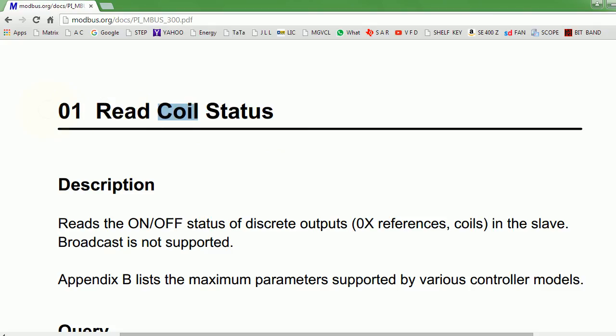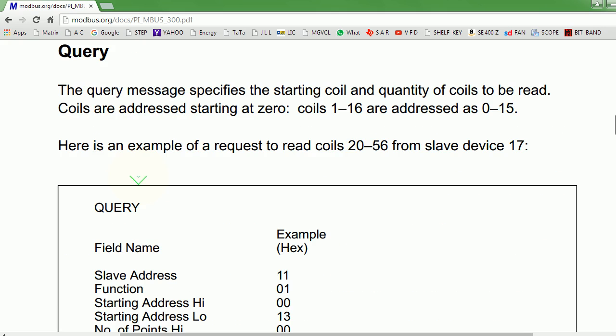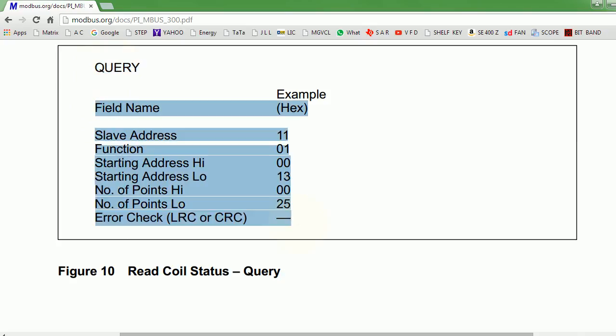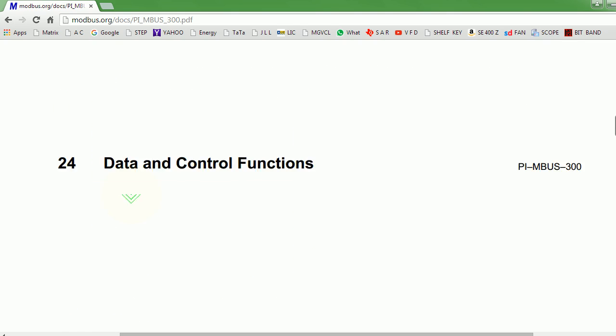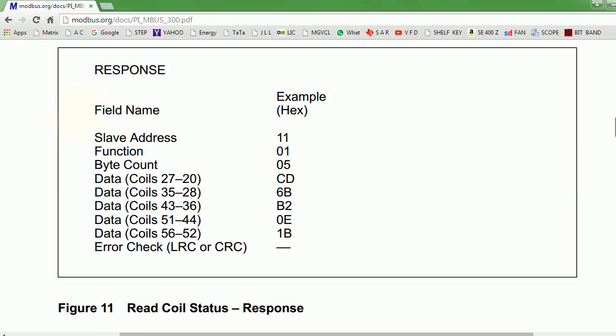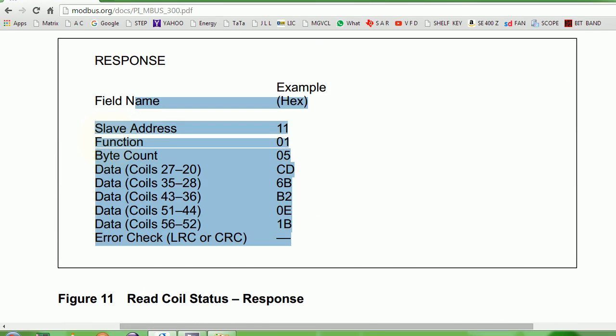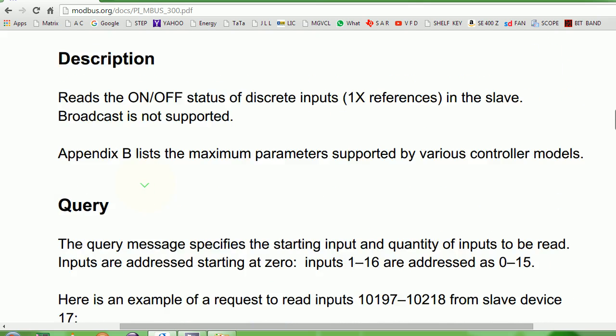To a PLC programmer, function hex 01 will really mean that I'm trying to read the value of a digital output value, which is a single bit. This is the query I'm supposed to be throwing at the PLC CPU. My laptop will send this to the PLC CPU, and then the slave has to reply. We will see how these numbers are related and which is what, taking a very deep look at all these things.